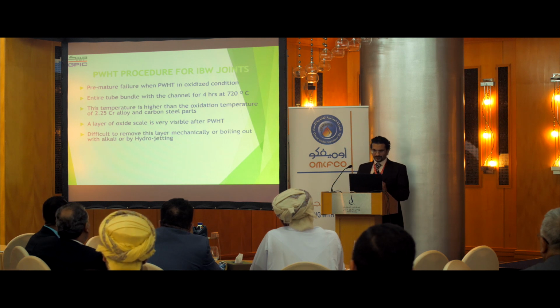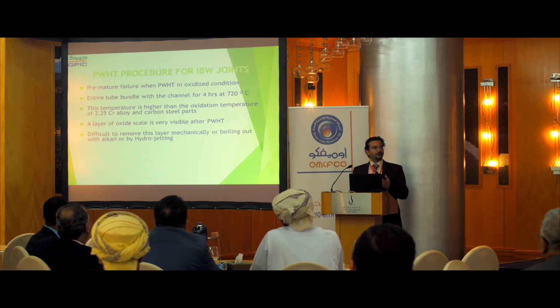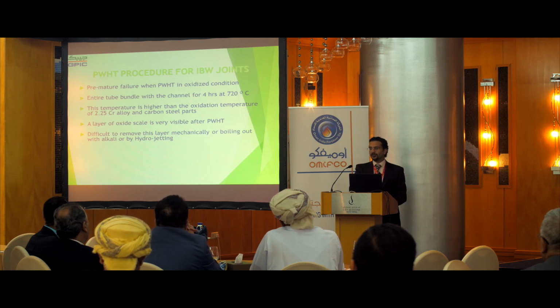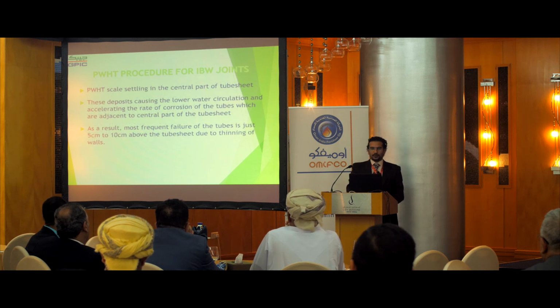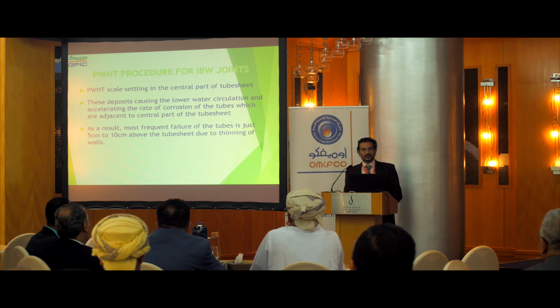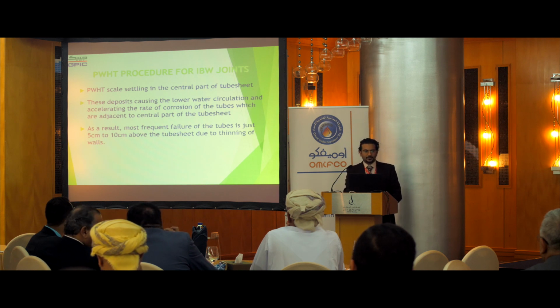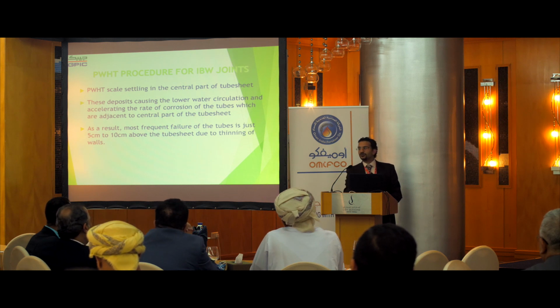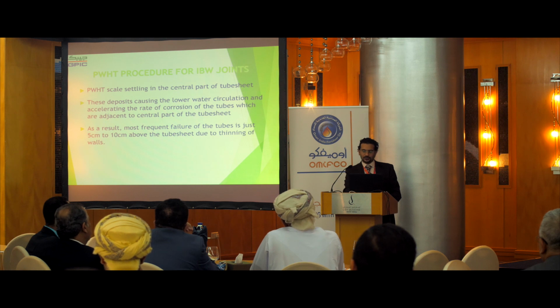They found some scale on the tubes afterward, which was hard to remove mechanically, with alkali, or with hydrojetting. This scale was settling in the central part of the tube sheet. It causes lower water circulation and accelerates the rate of corrosion under deposits. The most frequent tube failure is just 5 to 10 centimeters above the tube sheet.